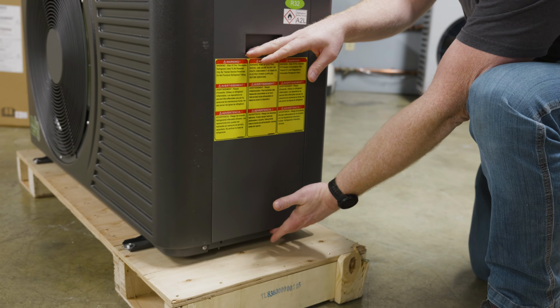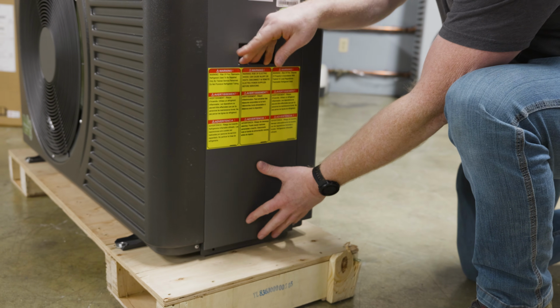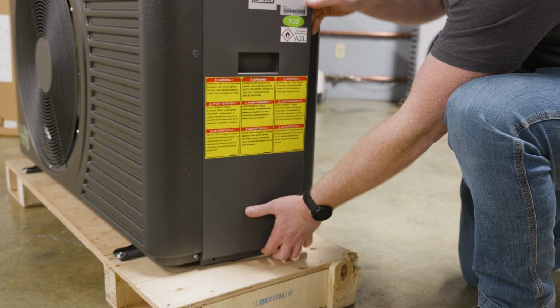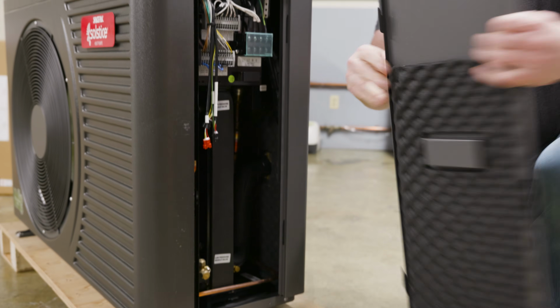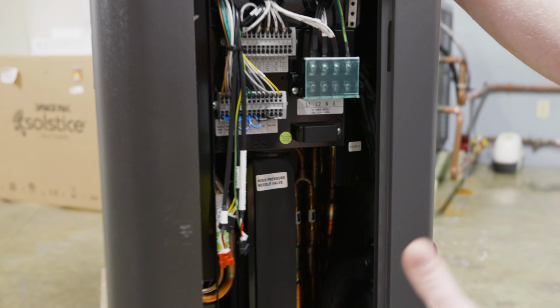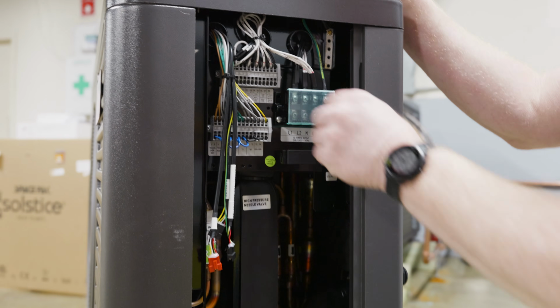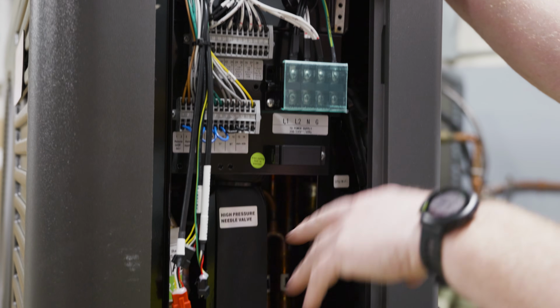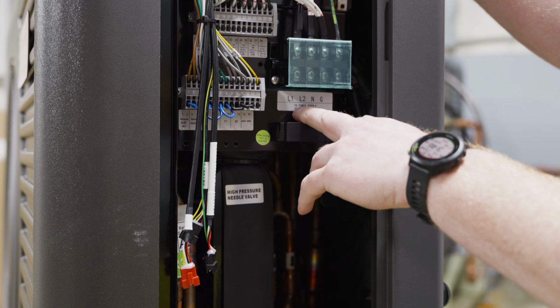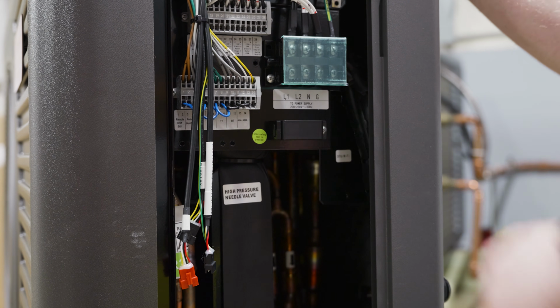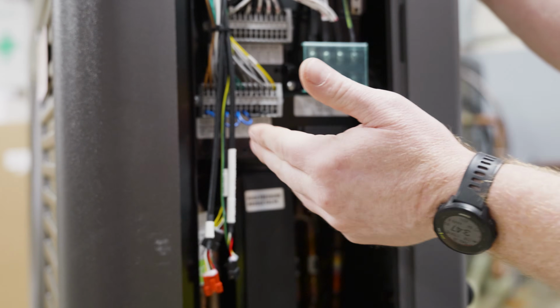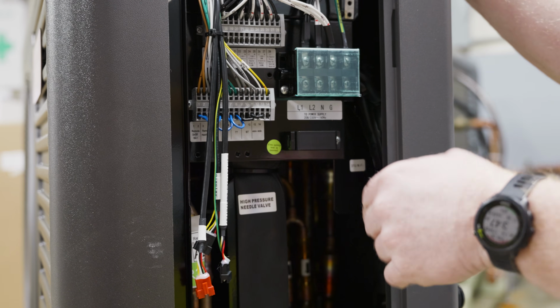Okay, so now that we talked about the information provided on the side of the unit, I've already taken 2 small Phillips head screws out of the bottom of this door. Slight push on the bottom, swing it out. Door pops right off, revealing the internals and the power connections of the system. On the right-hand side here, we have the high voltage connections. As you can see, L1, L2, neutral and ground, rated for 208 up to 230, 240 volts.